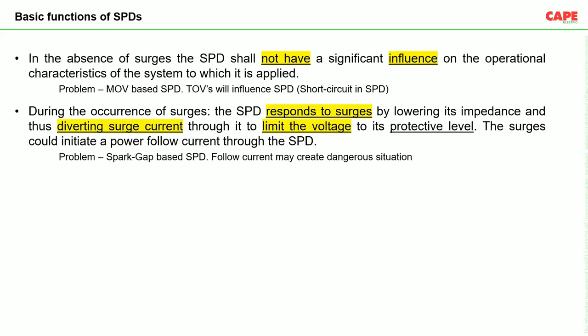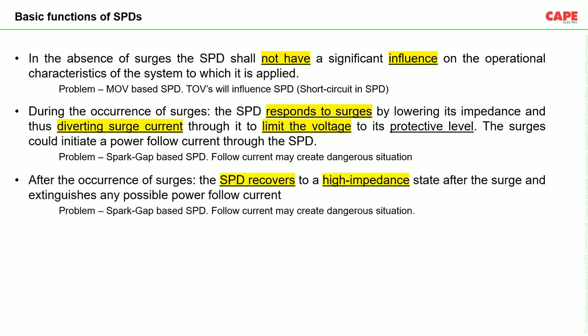Now, in case of spark-based SPDs, there can be an issue of follow current and that can create a very dangerous situation, that again we are going to discuss later. Third thing is, after the occurrence of surges, SPD recovers to a high impedance state and extinguishes any possible follow current. That means once the surge has gone, normally, as I told, SPD is in NO condition, a very high impedance condition. During the event of surges, it will create a short circuit. And once the surge is gone, SPD should again come back to its normal state and should not create any follow current. Again, in case of spark gaps, follow current can create a dangerous situation.